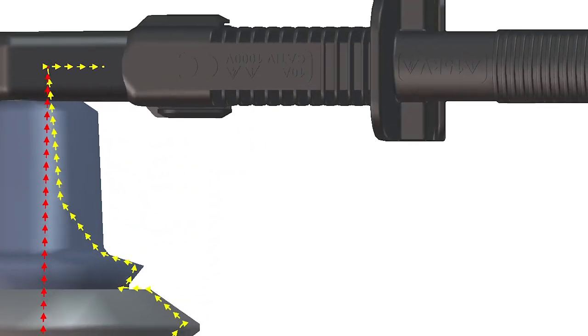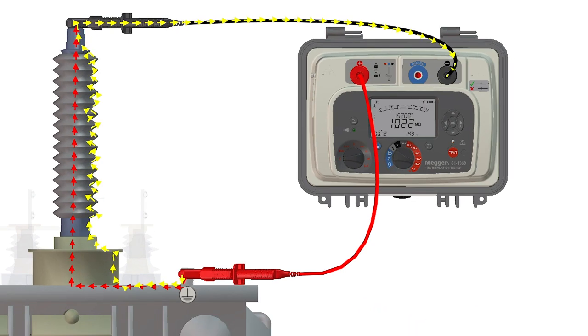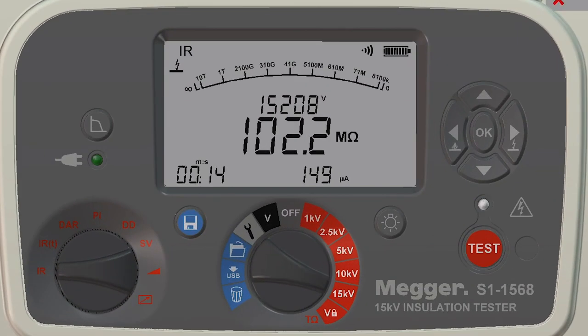In the diagram you can see that the insulation leakage combines with the surface leakage at the top of the bushing. This combined current is returned to the test instrument, providing a false low insulation resistance value.